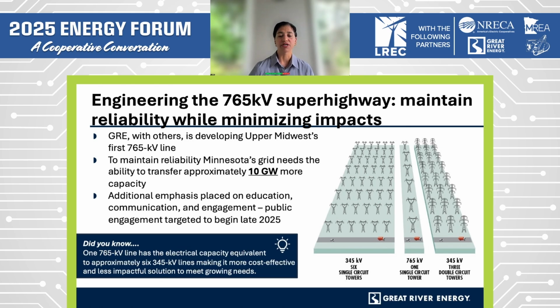When we look at the magnitude of the transmission needs in our region, this gets to tranche 2.1, which I showed you early on the map. When we evaluated how much impact, when we looked at the system and what it would take to match what would be needed, it would take a number of 345 kV lines, or we'd have to figure out a different approach. We looked at the impact to our communities of all those 345 kV lines, and we knew we needed a different approach. We started looking at 765 kV, and when we think about GRE and our membership geographically covering two-thirds of the state, we know that with 345, our communities are going to be overburdened by new infrastructure. That's why we started looking at 765 kV.